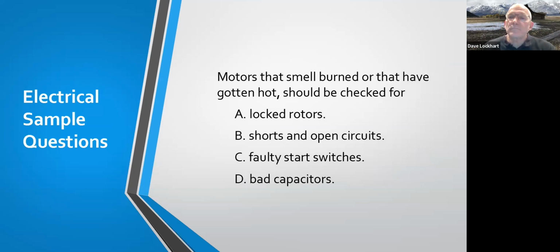meter testing on there. Motors that smell burned or have gotten hot should be checked for: A, locked rotors; B, shorts or open circuits; C, faulty start switches; or D, bad capacitors. Any ideas? Locked rotors, that would probably make your motor smell or burn, getting hot. Shorts and open circuits, definitely. Faulty start switches, no. Oh, nice job, Martin, thank you very much. Yes, B, shorts and open circuits. That's exactly it. A locked rotor could do that, but shorts or opens would definitely be one.